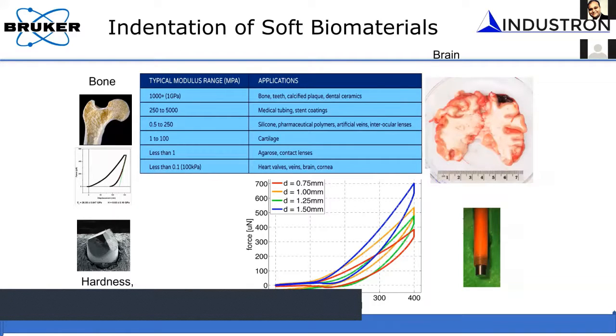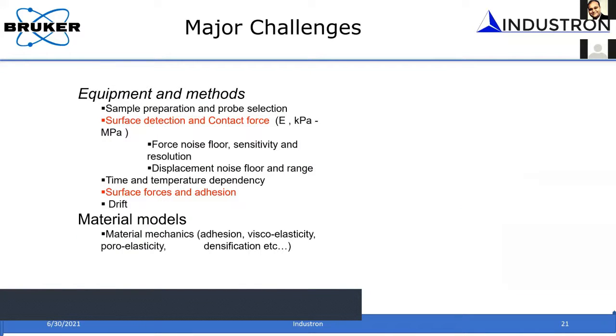So normally people use a bigger probe, sometimes a very flat-ended bigger probe, then apply the force and measure the displacement. You will still have high resolution in the vertical direction, about a nanometer, but the lateral resolution goes up. Sometimes people also do this experiment inside a liquid environment, which minimizes the adhesion characteristic. So there are ways to do that. What I mean is that the methods and techniques developed for measuring properties of metals and ceramics are good for hard materials, but not for soft materials. You need a different way of thinking and doing it.